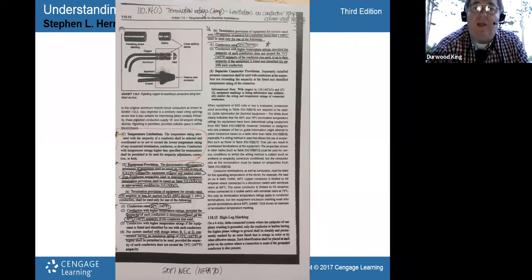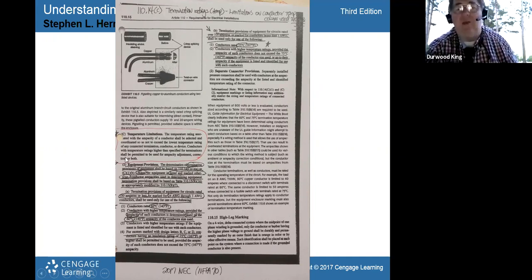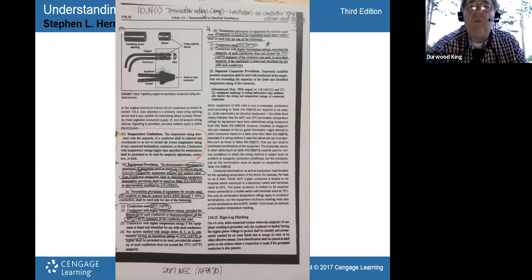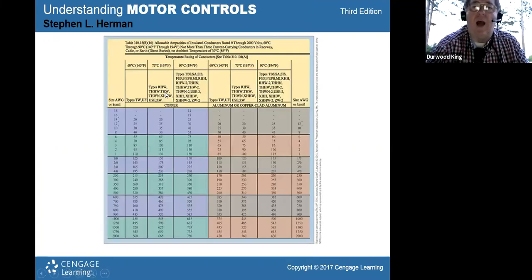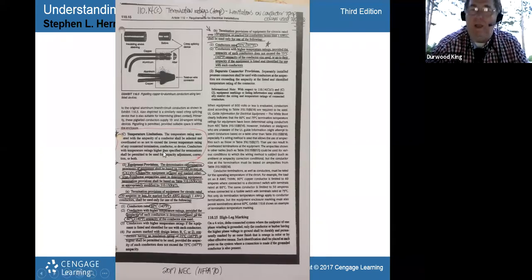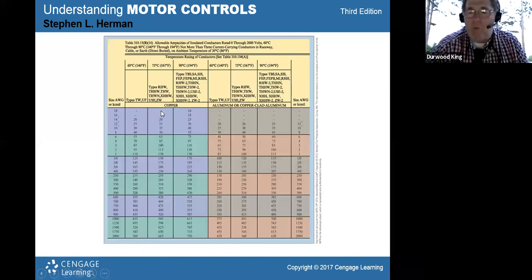Right there is where they mention in the code book about your terminal ratings. It tells you that the temperature rating of your wire has to be selected not to exceed the lowest temperature rating of any of your terminals or connections or devices. So it's basically whatever the weakest link in the circuit is on each end of the wire, the lowest rating of each end of the wire. That's what you got to go with when you choose what column you're going to choose the amp rating from. It has to be based on the weakest part of the circuit, which a lot of times would be the terminals. So some terminals are rated at 90. I've seen them rated at 90 Celsius, but I've seen more of them at 75.